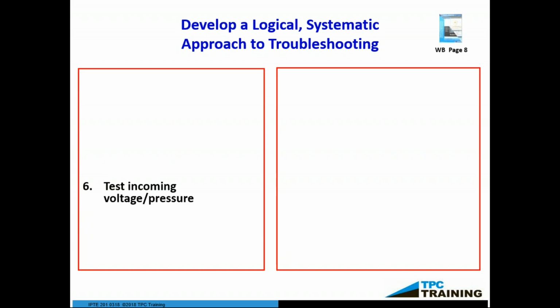On the electrical side, the first thing I always do is test my incoming voltage and/or pressure. If it's hydraulic, I make sure my pressures are there. If it's pneumatic, I check my pressures. If voltage, I check my voltage. Then I check my outgoing pressures and/or voltages. That's a pretty good indication: if everything coming in is good and everything going out is right, then I most likely have a mechanical issue. That's the idea, that's the way I look at it, a different type of thought process.